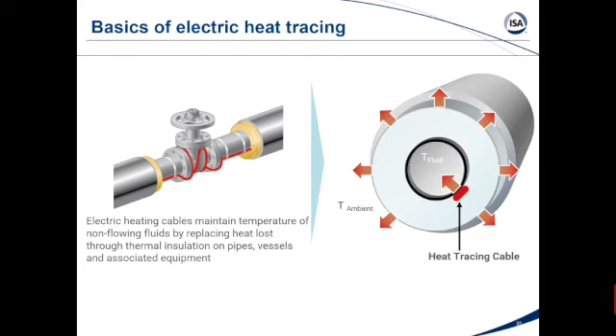So we have a 3-inch diameter line, water's in there, it's minus 25 degrees outside with 30 miles an hour wind. Your heat loss per straight linear foot of pipe is around 100 watts a foot, which is not manageable to try to address without insulation. You have to get that heat loss down. 100 watts per linear foot would be a tremendous load on any system and wouldn't really make sense, which is the reason and the real need for one of the main needs for insulation on the piping. What I mentioned earlier, that everything must be insulated.